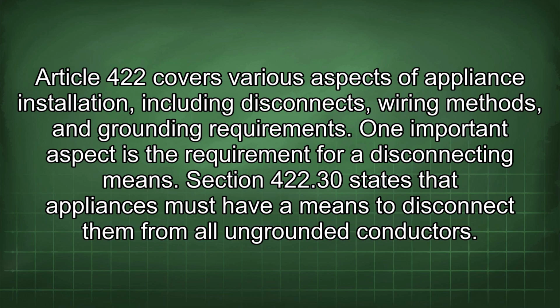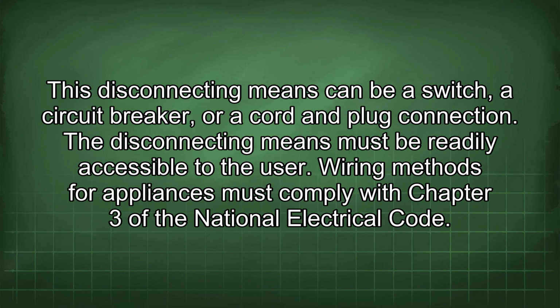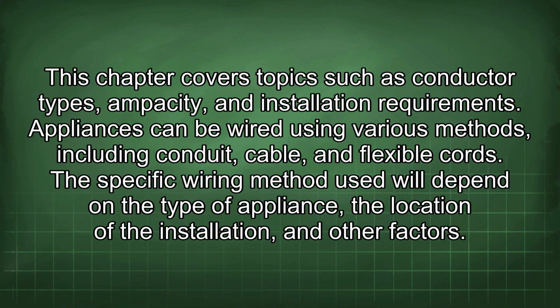Section 422.30 states that appliances must have a means to disconnect them from all ungrounded conductors. This disconnecting means can be a switch, a circuit breaker, or a cord and plug connection. The disconnecting means must be readily accessible to the user. Wiring methods for appliances must comply with Chapter 3 of the National Electrical Code. This chapter covers topics such as conductor types, ampacity, and installation requirements. Appliances can be wired using various methods, including conduit, cable, and flexible cords. The specific wiring method used will depend on the type of appliance, the location of the installation, and other factors.